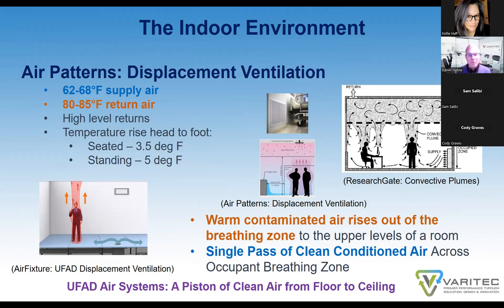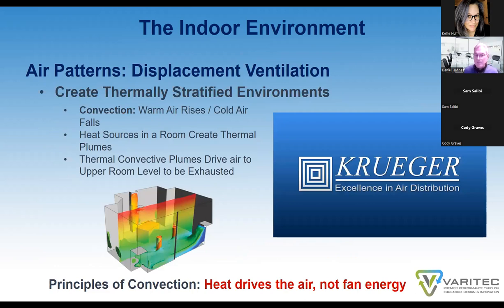One of the ideal ways to handle displacement ventilation and to create a thermally stratified environment is to look at underfloor air systems, where the air is actually supplied through the floor plenum itself. Because in this design, you have diffusers located throughout the floor of a space, and a single piston of clean conditioned air is drawn up across an occupant's breathing zone to the upper levels of the room where it's exhausted from the space.